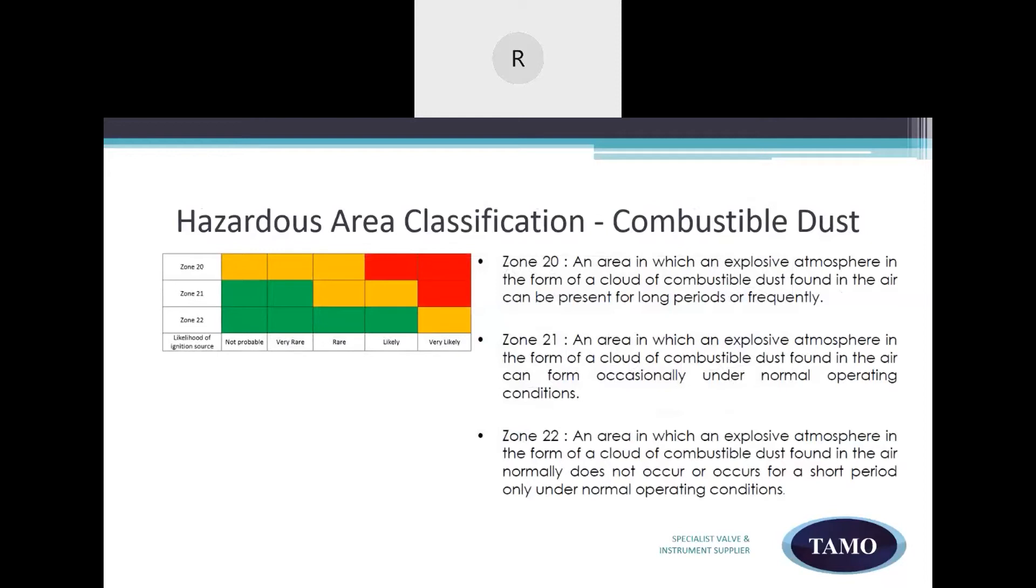Let's look at the hazardous area classification for combustible dust. The zone system also covers combustible dust under Zone 20, Zone 21, and Zone 22. Dust zoning is much simpler than zoning for gases and vapors. This is partly because dust rarely moves farther than a meter from the source of release due to its tendency to settle on the ground. The zones are set as Zone 20 is the high probability of explosive atmosphere, Zone 21 is medium probability, and Zone 22 is the lowest probability.